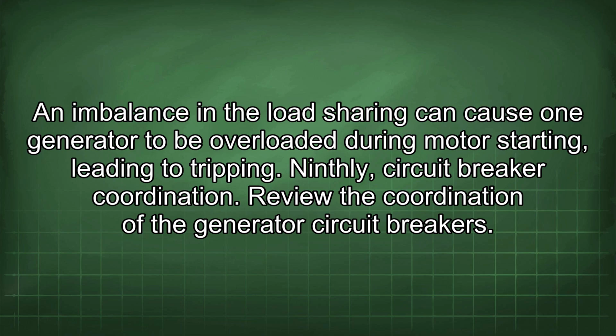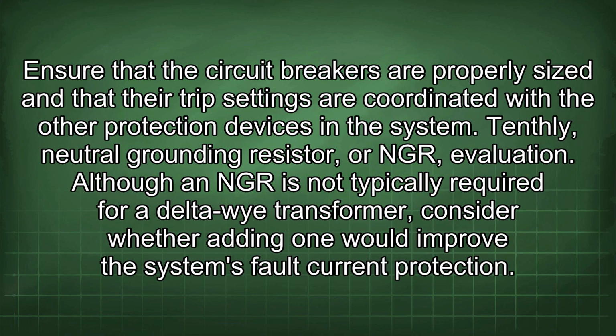Ninthly, circuit breaker coordination. Review the coordination of the generator circuit breakers. Ensure that the circuit breakers are properly sized and that their trip settings are coordinated with the other protection devices in the system.